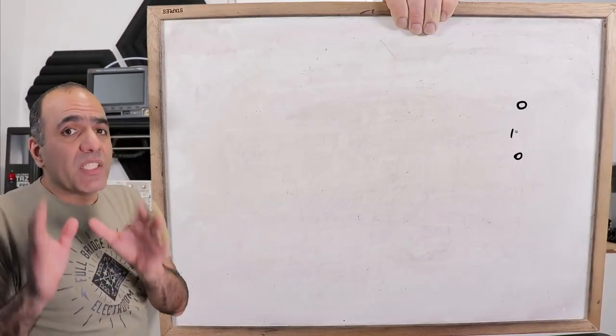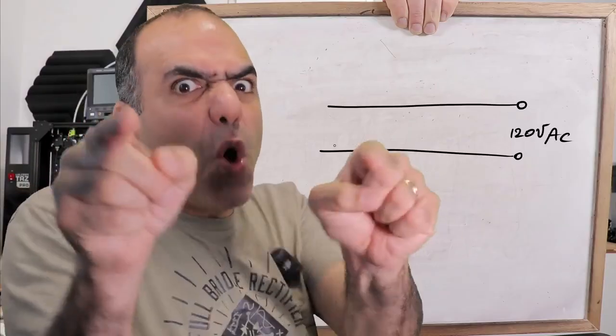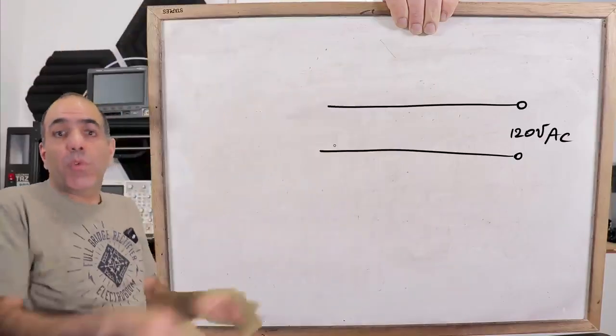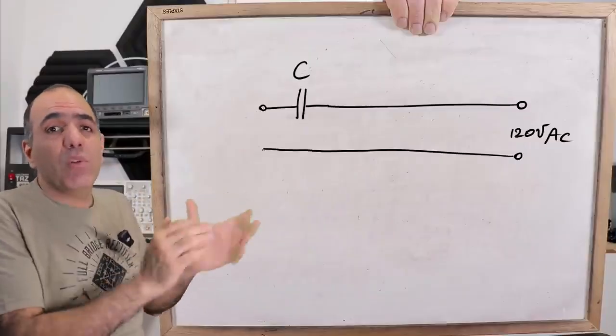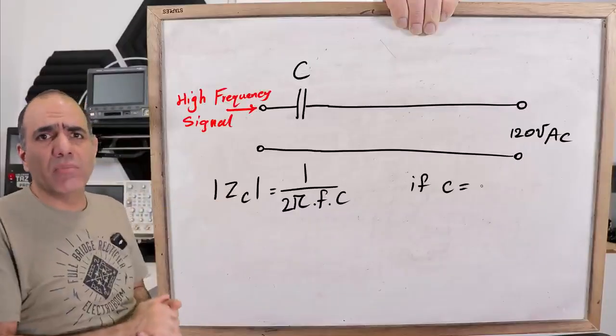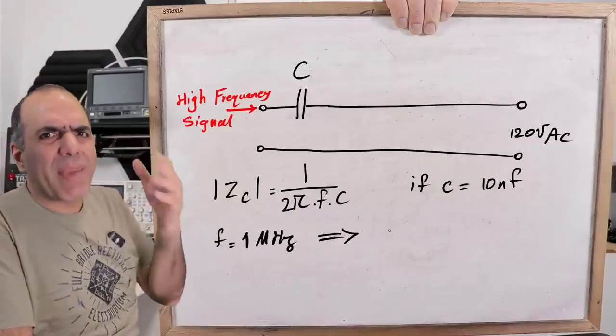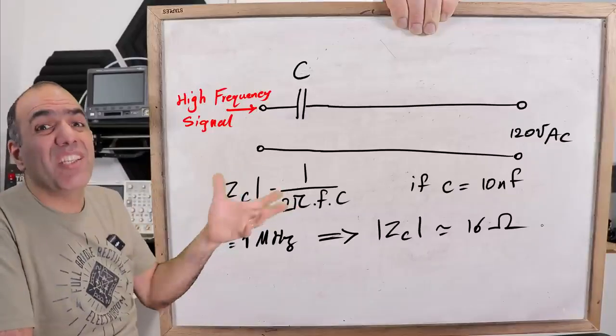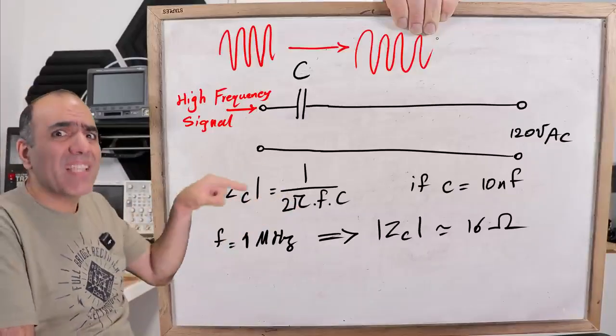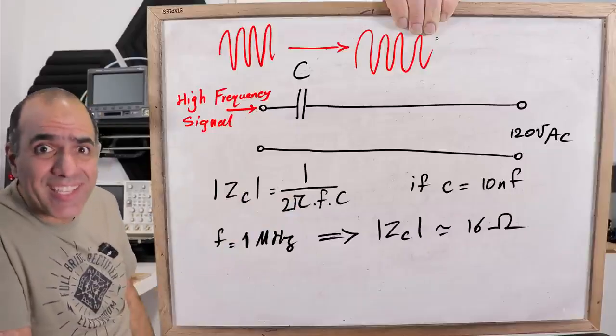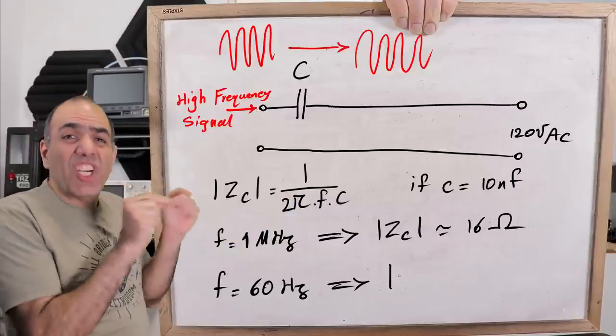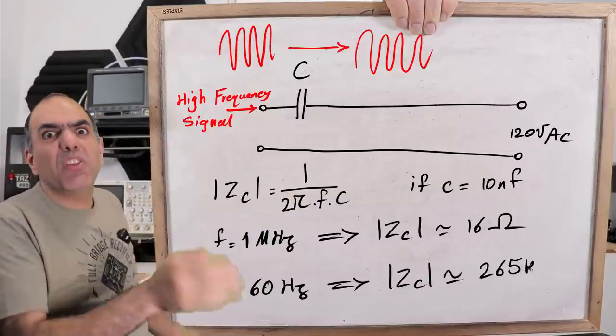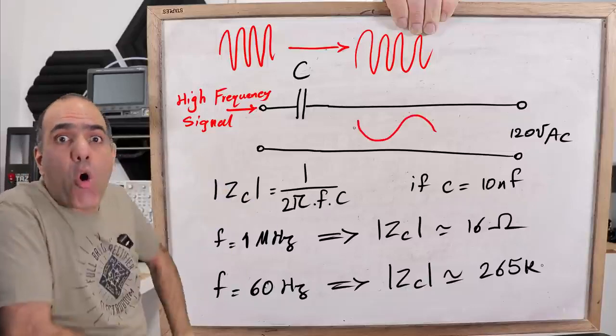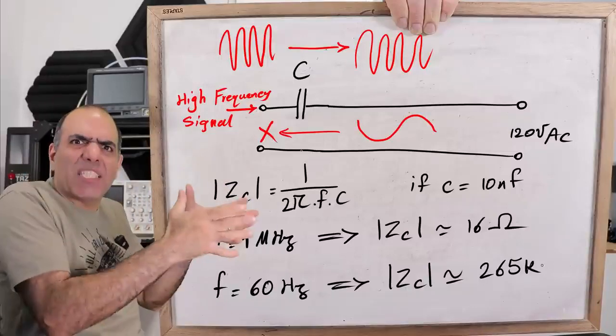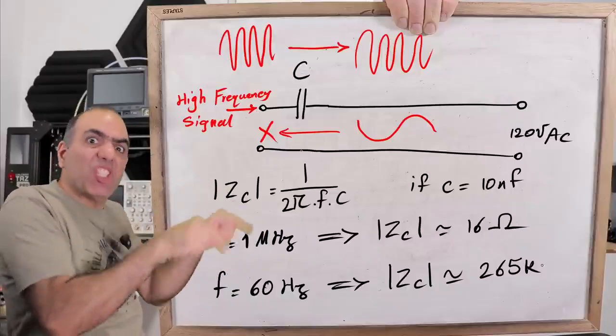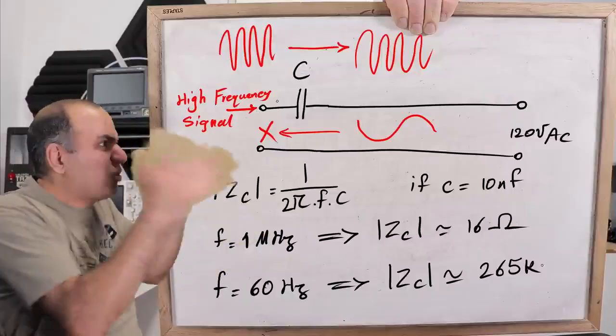To inject my signal into the live wire, we don't connect directly, but pass it through a small high voltage capacitor, like 10 nanofarad. If our signal is around 1 megahertz, the capacitor impedance would be around 16 ohms, and the signal passes through easily. But the impedance for the 60 Hz line frequency would be over 260,000 ohms, easily blocked by the capacitor, so it can't hurt my function generator, so we should be able to...